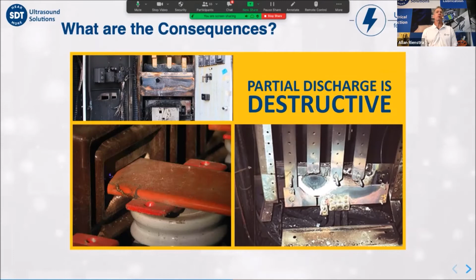Now, the consequences of allowing partial discharge to progress include damage to assets, pole fires, explosions, and deadly arc flash. And as I said at the opening, unreliable assets not only cost millions in downtime and repairs, they possess the potential to maim and to kill our colleagues. So ultrasound presents kind of a triple win solution. It reduces the risk of arc flash exposure. It ensures equipment reliability, and it also allows inspectors to work at a safe distance from high voltages. And this video that we're playing now, that's just a dummy. That's not a real human being, thank goodness.